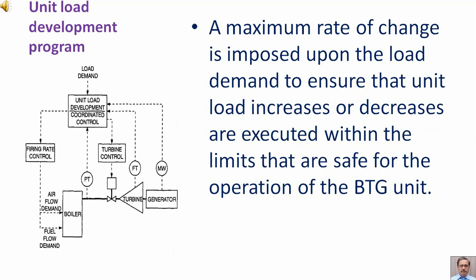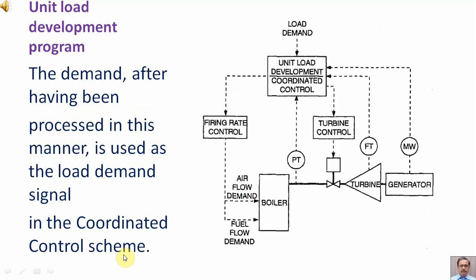A maximum rate of change is imposed upon the load demand to ensure that unit load increases or decreases are executed within the limits that are safe for the operation of the boiler-turbine-generator unit. The demand, after having been processed in this manner, is used as the load demand signal in the coordinated control scheme.